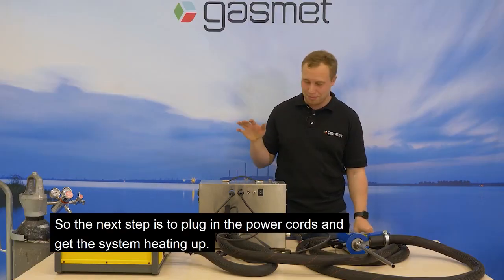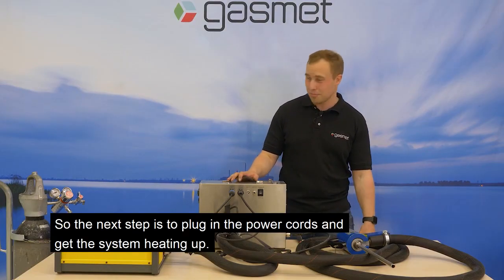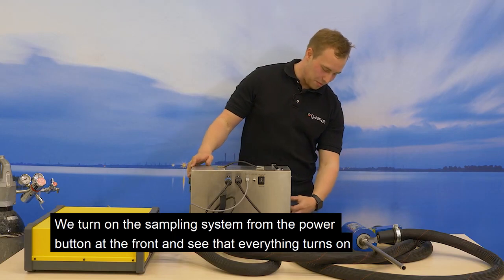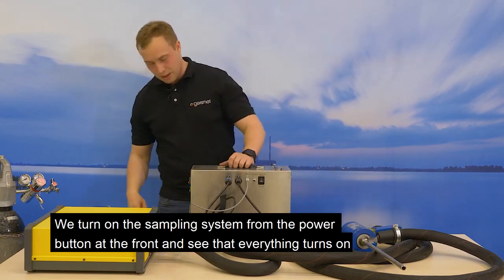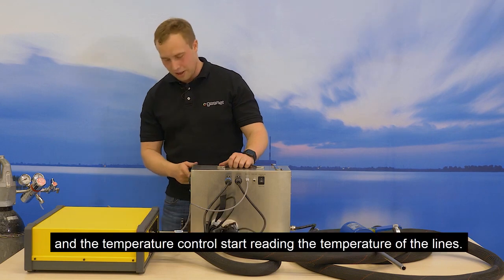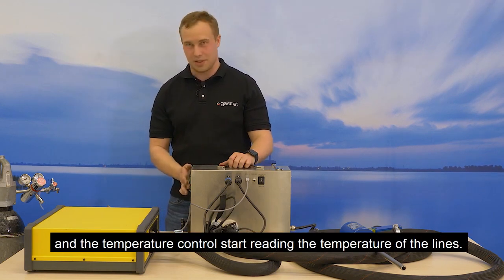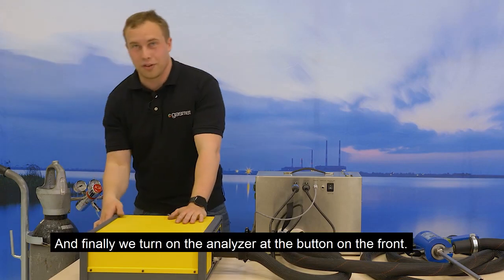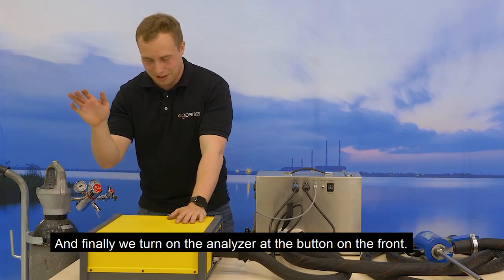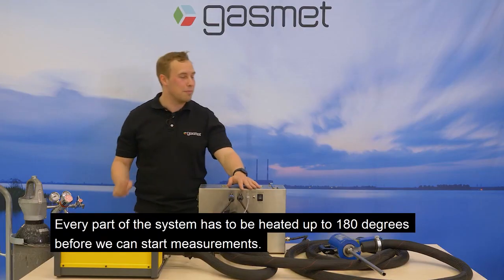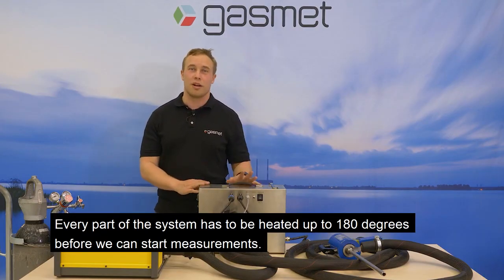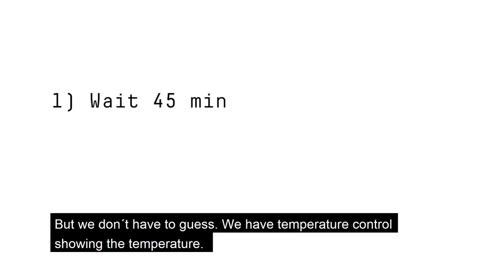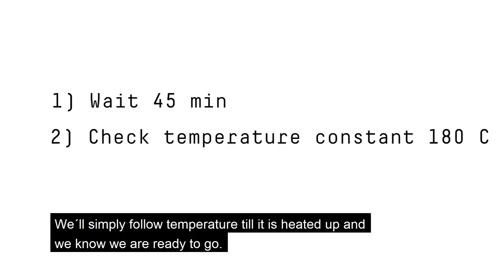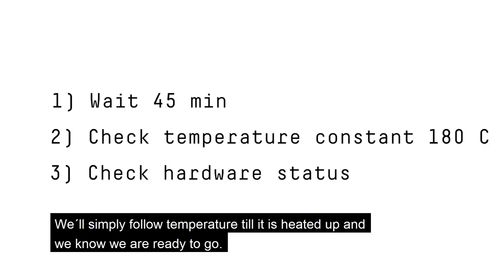So the next step is to plug in the power cords, get the system heating up. We turn on the sampling system from the power button at the front and see that everything turns on and the temperature controllers start reading the temperature of the lines. And finally we turn on the analyzer at the button at the front. Every part of the system has to be heated up to 180 degrees before we can start measurements. But we don't have to guess, we have the temperature controllers showing the temperature. We'll simply follow the temperature until it's heated up, and then we know we're ready to go.